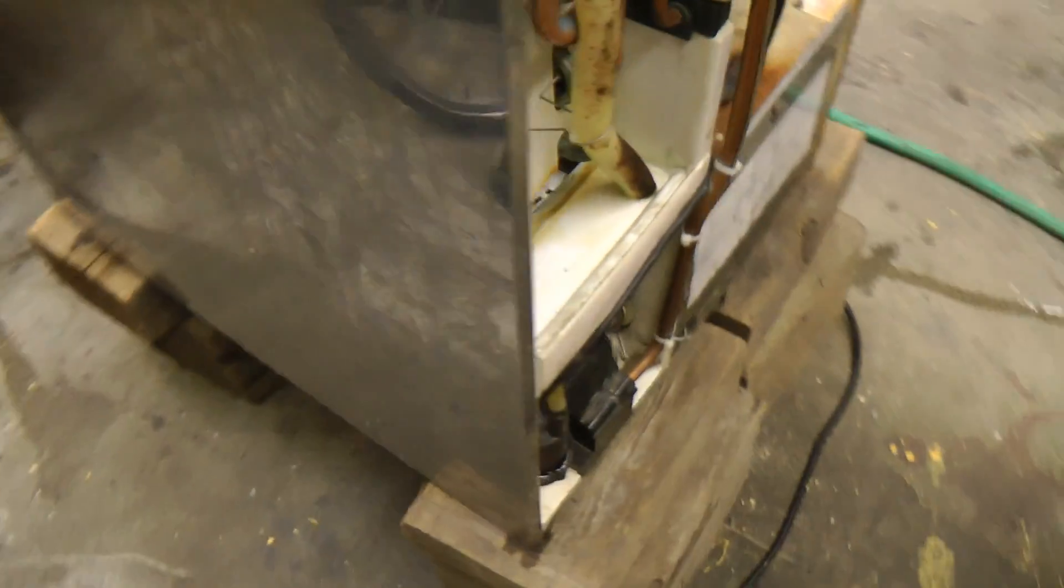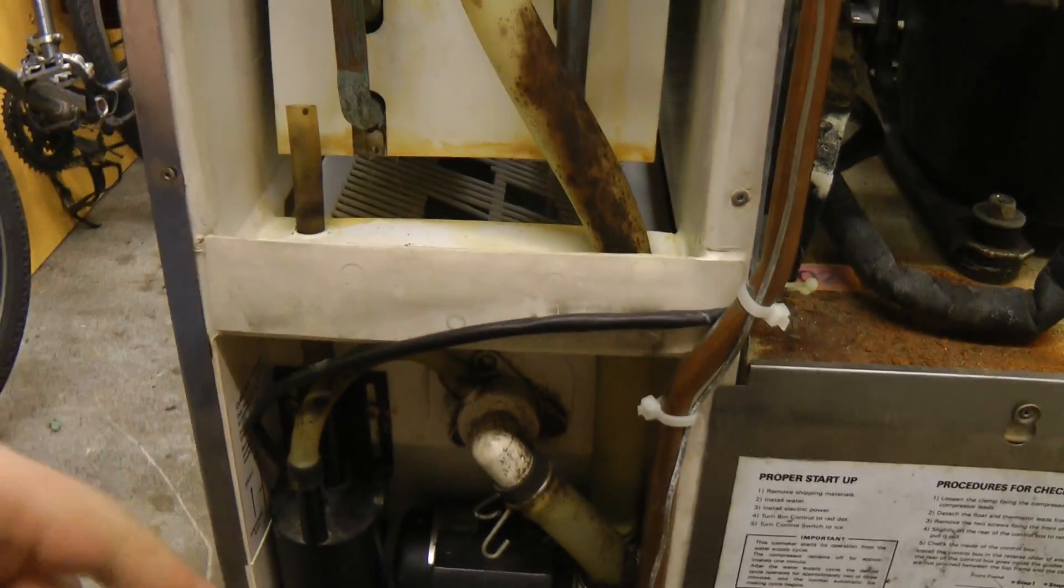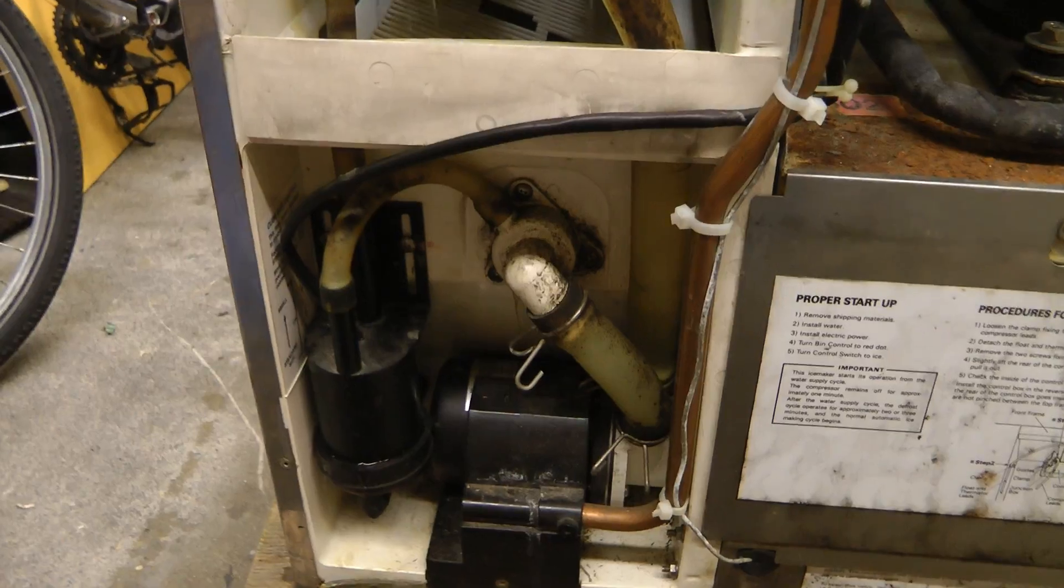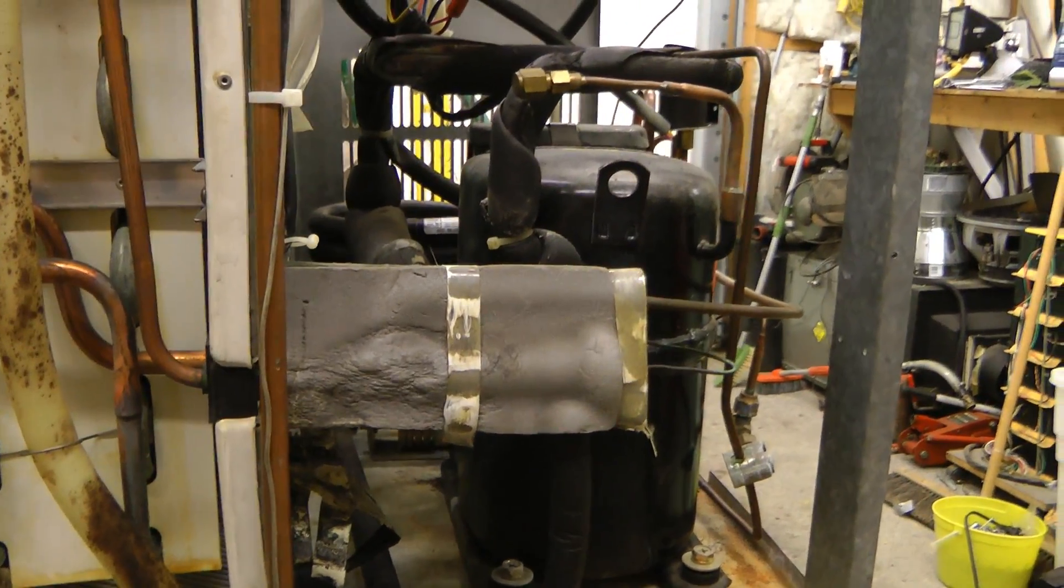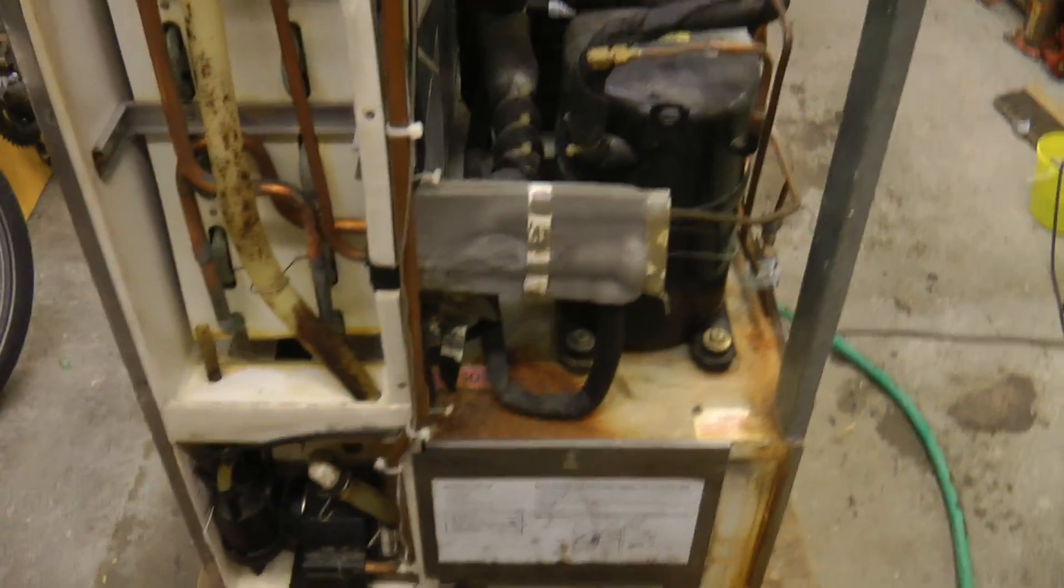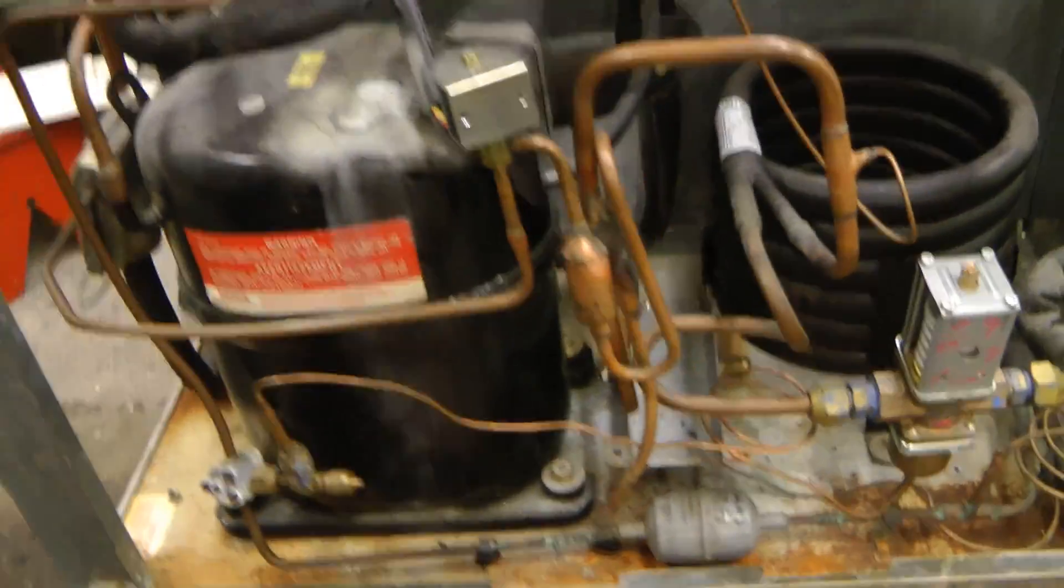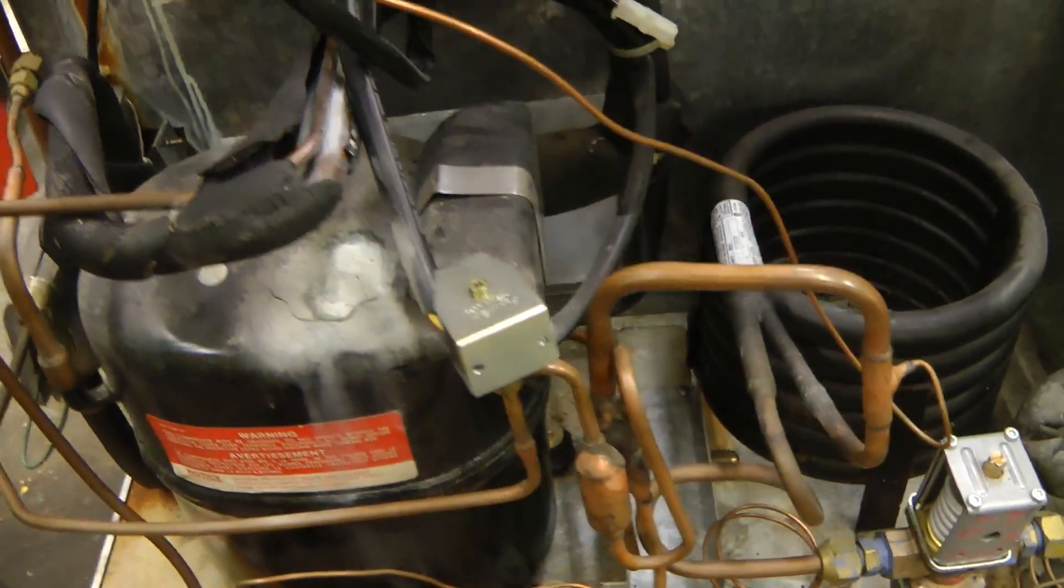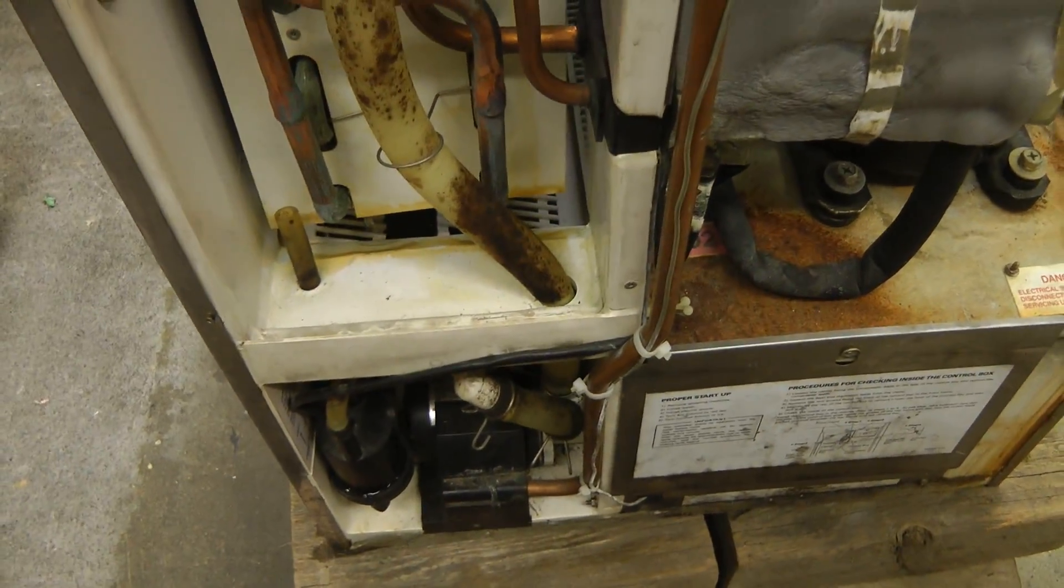So that because as the ice freezes the ice is very pure and the impurities get left in the water. And if you didn't cycle through, the impurities would build up and cause problems, the hard water build up in the water tank. Then after it fills apparently it's going to run a defrost cycle for a minute or two with that bypass valve open. Then it's going to go into actual cooling mode. There's the defrost. You can hear sort of a hissing as the gas is flowing through. It could very well just be nitrogen that they left in the system but we'll see.